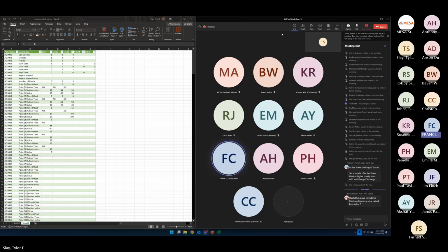Yeah, this would be generation following, which is one of the functions. You'd be essentially following the generation with a certain target where you wouldn't do anything until the PV system has reached the target and is now generating more. Then the battery would start charging to keep the PV system from exporting more.